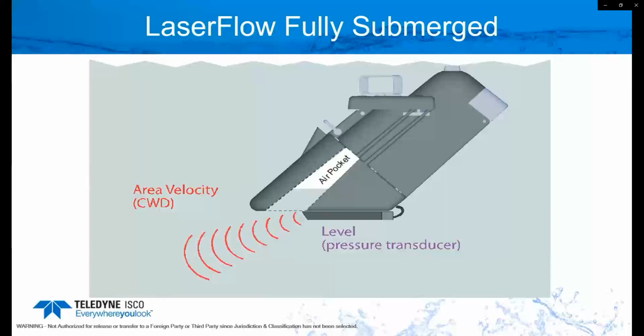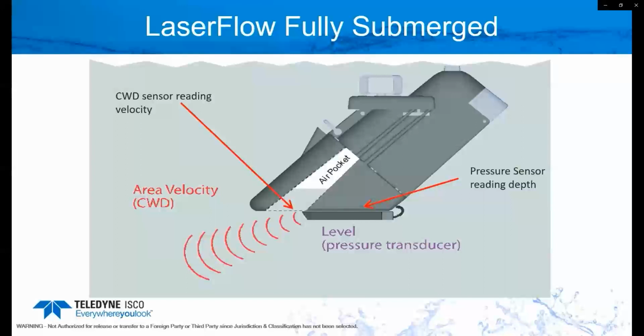So there are other ones out there that use electromagnetic. We use continuous wave, but most use some sort of pressure sensor to calculate the total submergence. So if I'm in a 54-inch pipe, it would tell you you're at 54. As it goes all the way up, it says I'm 55, all the way up to whatever it is. Now you have a very accurate measurement of the submergence in that manhole.